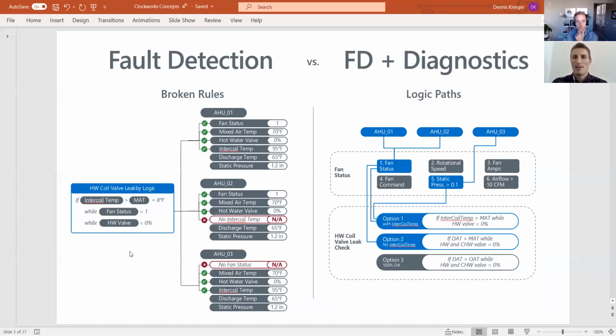This instantly breaks down once you've seen more than one controller. There's a lot of diversity in the type of BACnet objects you get from an AHU controller, and inevitably your rule set has to be customized for each diverse application. If you don't have an intercoil temp, how are you going to detect the same thing? If this unit doesn't have a fan status, how do you know when it's on? These seem like simple challenges, but they require a lot of sophistication in how you route the analysis and map it against diverse controller types, and a simple rule simply can't do that.